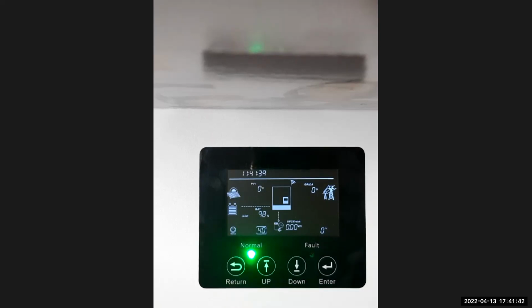So that means if you have a small farmhouse that only has a small fridge that's running, you can add 2-3 kilowatts of panels on the roof and only this unit. If the sun is shining and you have sufficient panel power, you don't have to have a battery in off-grid mode to supply the loads to your house. But that's a very tricky situation. Most of the time, if there's any load changes, the inverter won't handle it because your power from the panels can't handle load changes. So that's a setting that you're rarely going to use.